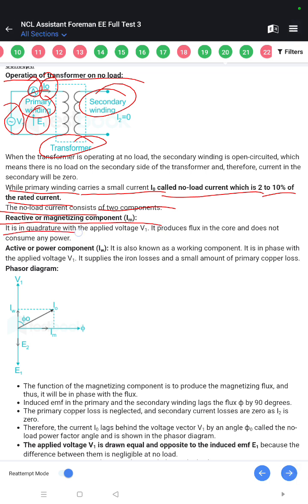It is in quadrature with the applied voltage V1. It produces flux in the core and does not consume any power. The second is the active or power component Iw. It is also known as the working component. It is in phase with the applied voltage V1. It supplies the iron losses and a small amount of primary copper losses.